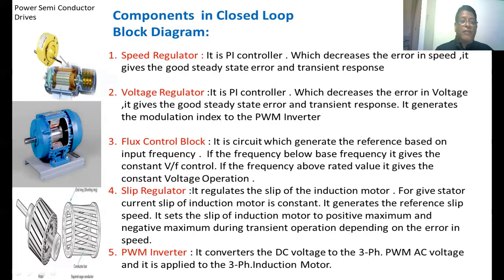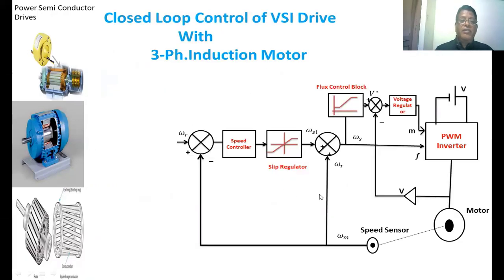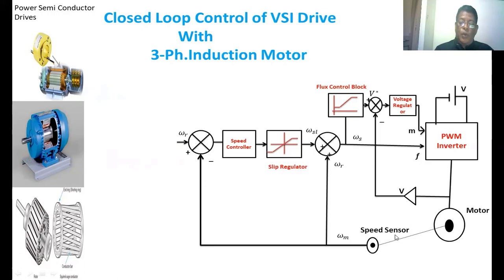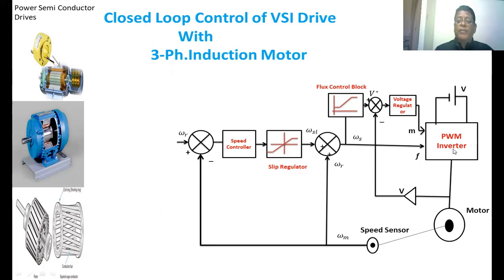Now we are going to see the closed-loop block diagram of a three-phase induction motor. This is the closed-loop control of a VSI drive. The three-phase induction motor consists of a speed sensor. The rotor and stator of the induction motor are shown. This is the PWM inverter — its output is given to the motor. This is the input DC voltage, the reference speed, the speed controller, the slip regulator, the flux control block, and the voltage regulator. The closed-loop control consists of an outer speed loop and an inner slip speed loop, because the slip of the induction motor highly depends on the current taken by the induction motor, so indirectly we are controlling that current.